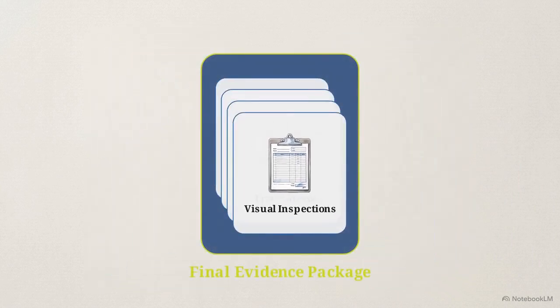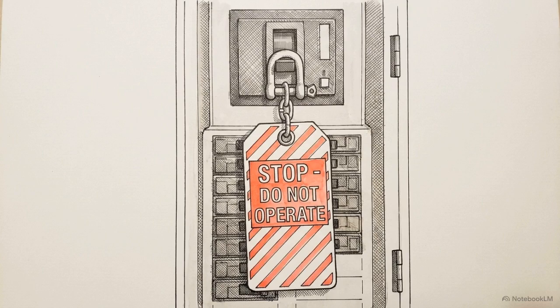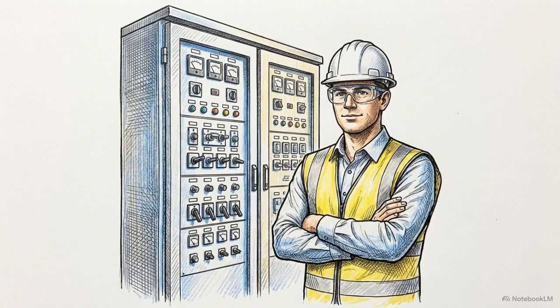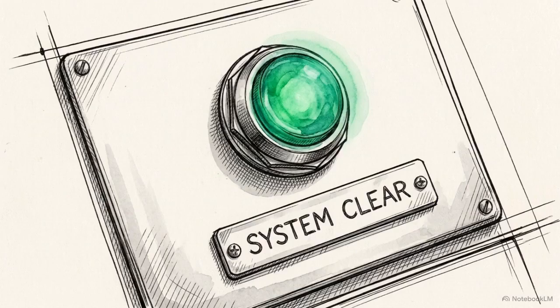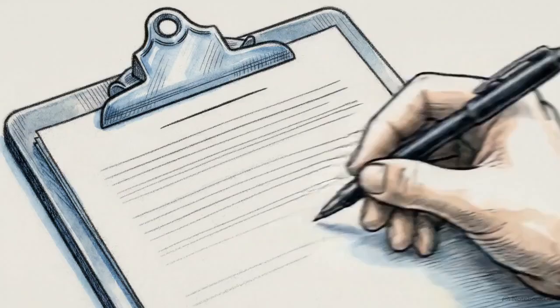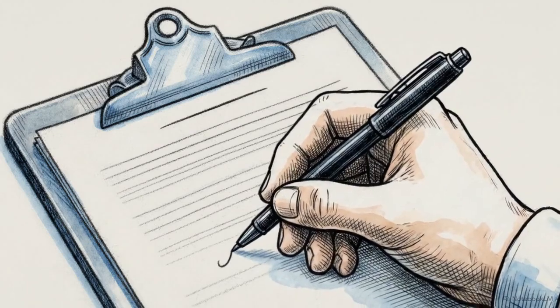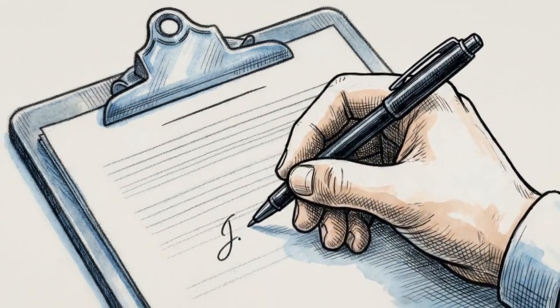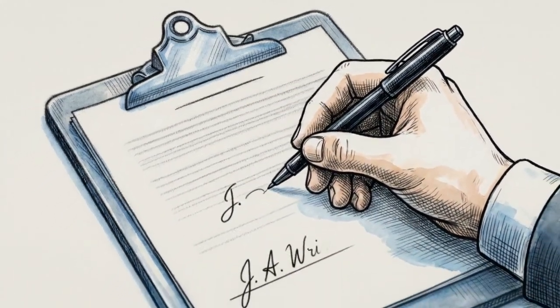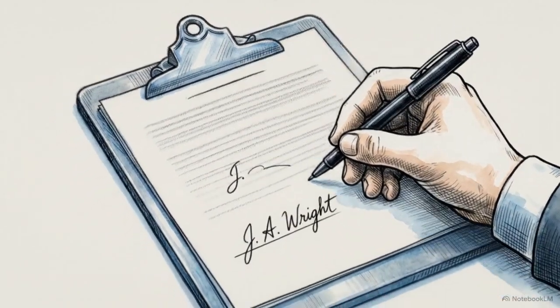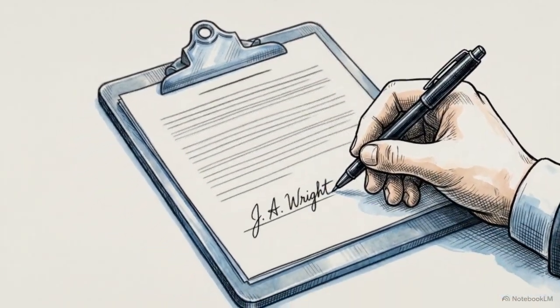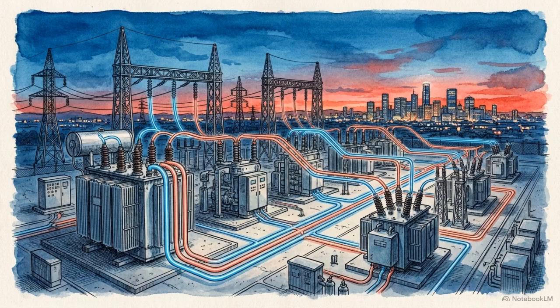We then reach the ultimate operational hold point. An operations witness must physically inspect the panel, confirming that it has returned to normal status. All test configurations have been removed, and there are 0 active alarms. A grid asset only achieves service release when every test result, log entry, and legal sign-off proves a flawless match to the engineering intent. Only then can the system safely interface with the live electrical grid.